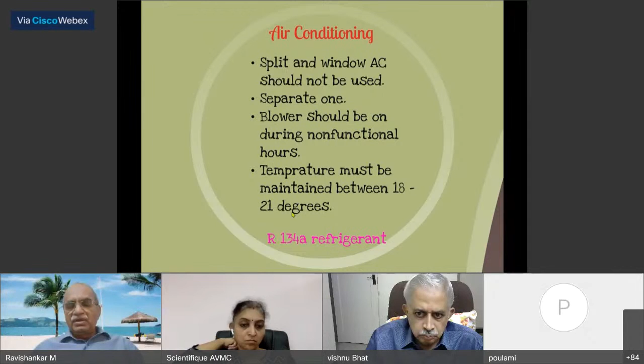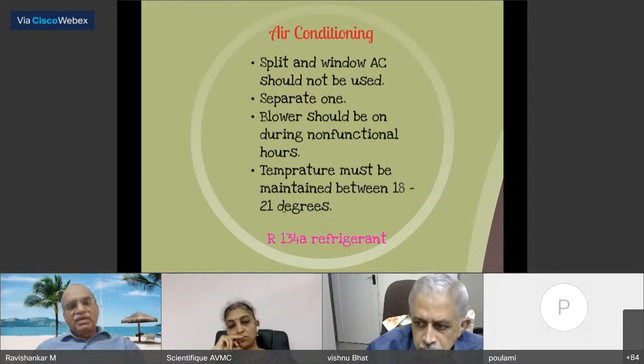Okay, for air conditioning, I have already told you the split air conditioning should not be used. It should be a separate one. Blower should be on during non-functional times, and the temperature must be maintained between 18 to 21 degrees. And the refrigerant that is used should be of the R134A grade so that it does not add to the load of greenhouse emission gases.